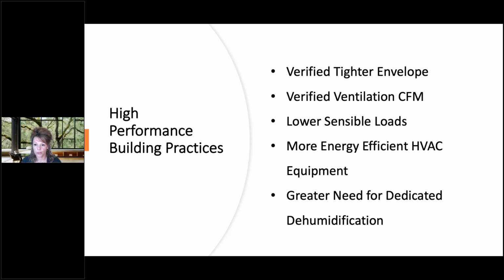We have lower sensible loads in our homes. We have more energy efficient HVAC equipment. We have a greater need for dehumidification in a large part of the country. We say green grass climates. So if you look outside during the spring, summer, and fall, and you see green grass, most likely you're going to need some form of dehumidification. That could be that maybe your AC at peak loads is going to handle that, but the shoulder seasons is very challenging to handle that latent load.